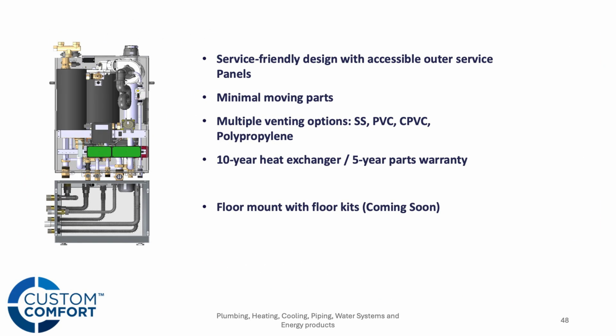The biggest feature of this boiler that you're going to appreciate is the serviceability and accessibility of it. And we'll look at that a little bit deeper later on. But if you need to repair anything on this boiler, you can get at it by the access panels on the outside of the boiler. Same thing on the venting. Again, stainless steel, PVC, CPVC, polypropylene. We'd rather see stainless steel, CPVC, or polypropylene. We'll talk about the warranties a little bit later as well, but 10 years on the heat exchanger, 5-year parts warranty on this fire tube combi.